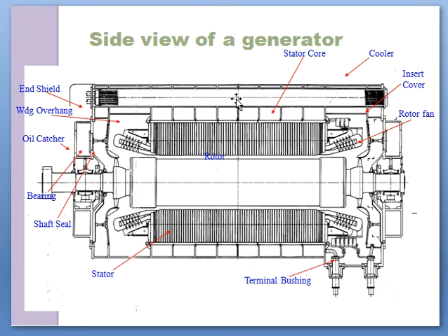After a brief explanation about the different parts of a generator, now I think it is easy for you to identify the different parts from this block diagram. The outermost part, this is the stator frame. Just below the stator frame, we have made space for the windings. So this is the stator core, which has slots, and the windings are there in the slots.